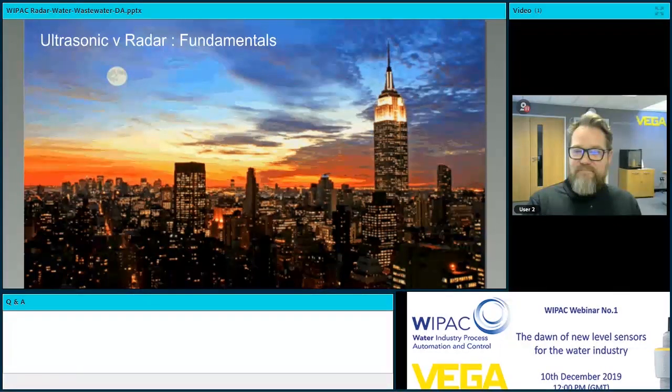So just to finish this part, I'll give you a direct physical comparison. We're going to talk a little bit about the difference between radar and ultrasonic. It's the difference between sound waves and microwaves or radio waves. They travel at the speed of light. Obviously, sound waves travel at the speed of sound. An ultrasonic sound wave runs at about 343 meters a second in dry air at 20 degrees C. And a radar radio wave is traveling at the speed of light, which is nearly 300,000 kilometers a second. And no temperature or humidity values are needed there.